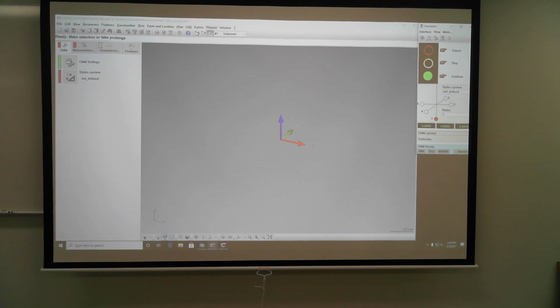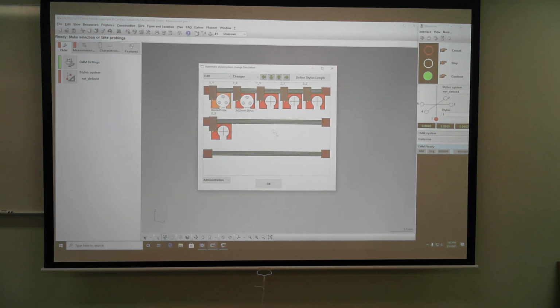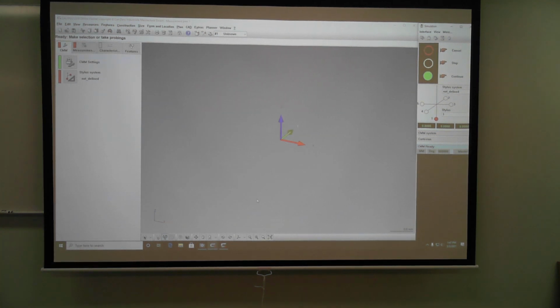But if you're online, this automatic A is how you're going to do your probe change. So for all of you, you'll click on that A. You'll left click on your 3 by 50 millimeter stylus, and then you'll right click and say load stylus system from holder. You'll see your machine do an actual tool change.